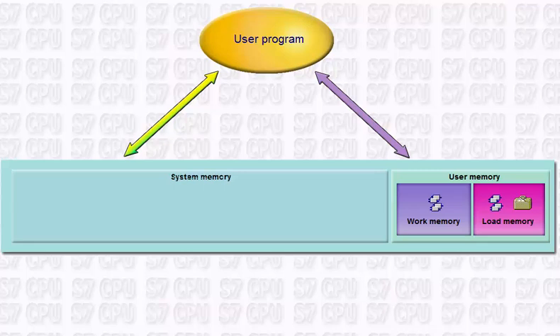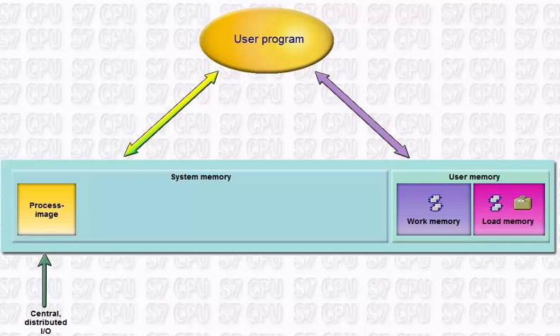The system memory contains the following sections. The process image, which is the interface to inputs and outputs of the module. At the beginning of each program cycle, the operating system automatically ensures that the complete image of all parameterized inputs and outputs is updated and their status filed in the so-called process image.